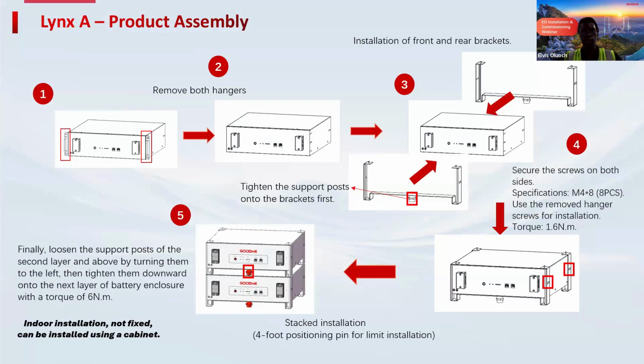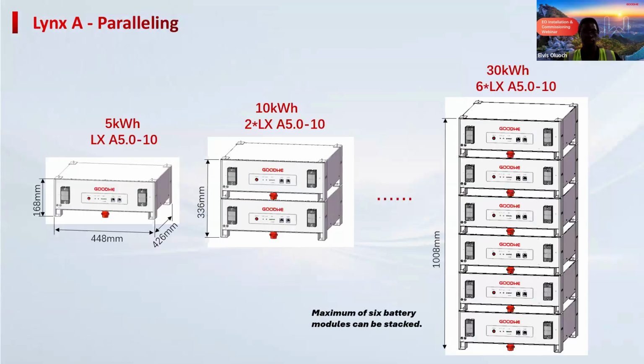This is just a quick go-through in case you're doing the installation for the battery. It does come with the hanger, which we will see as we unbox. With the hanger, you're able to use it as a bracket. Therefore, you can stack them on top of each other. As you stack them, the maximum you can do is up to 6 batteries. This is mainly because of the weight, as one battery is almost over 40 kilograms. So that it does not crush the bottom one, it's recommended to put a maximum of 6. So in case you're doing the 15, you'll have one tower with 6, a second tower with 6, and then the final tower with 3 batteries.